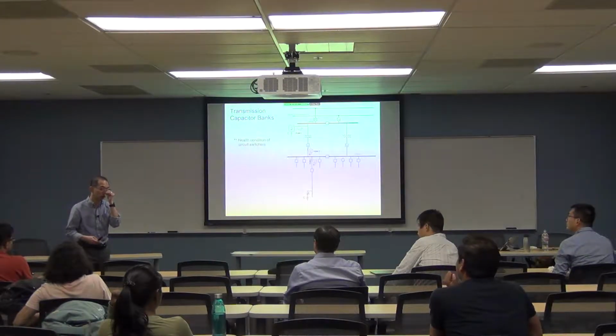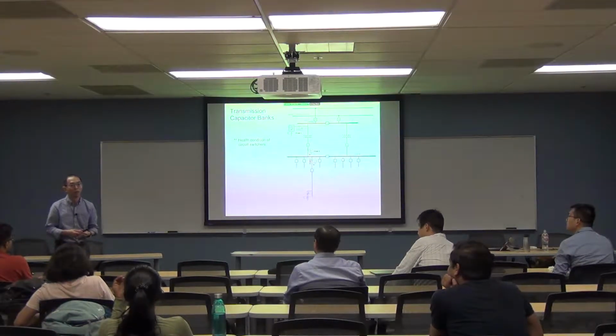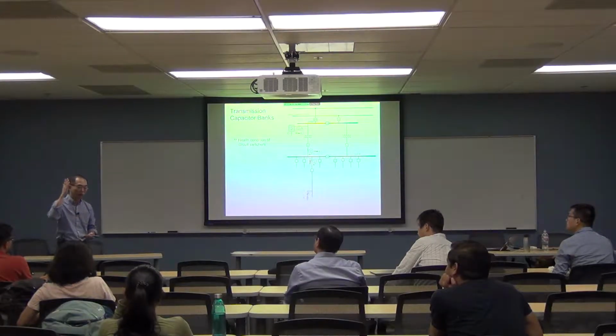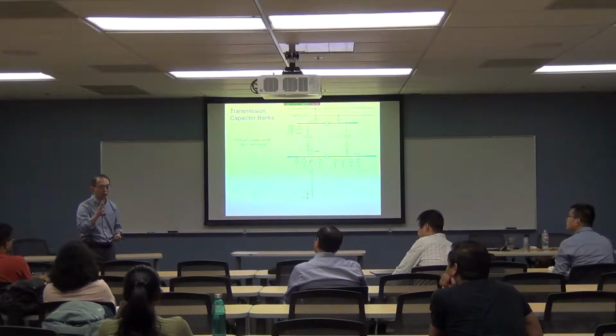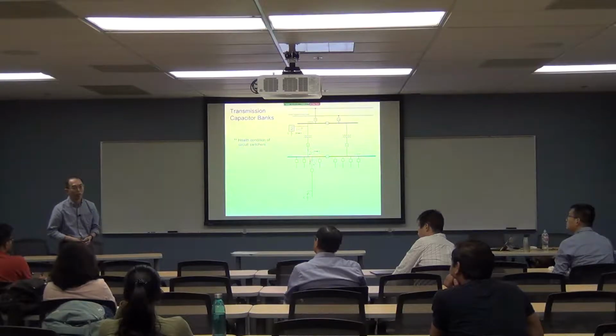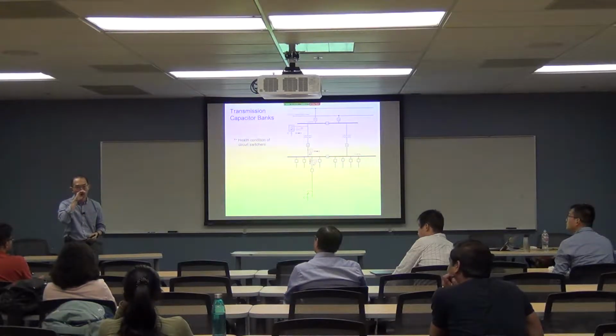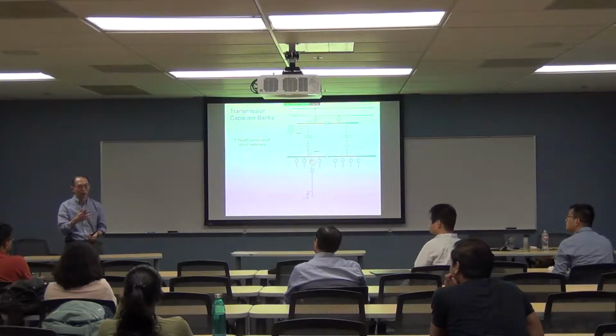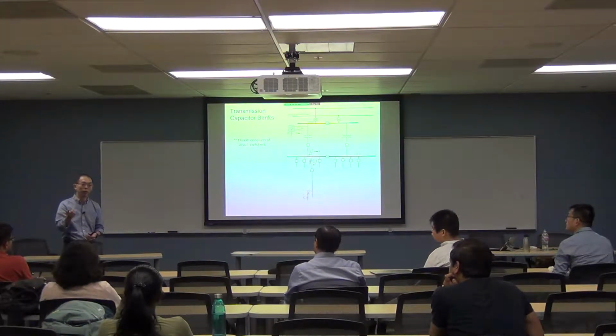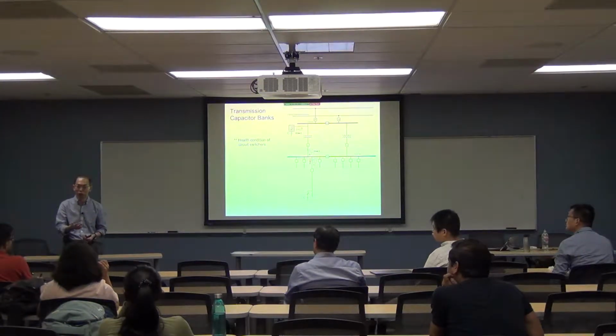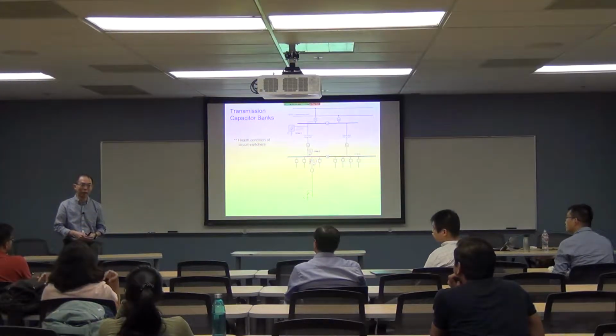Voltage and current analysis, based on the first derivative of the switching instant of the transients. That can only be done if you have sufficient number of samples per cycle, like 256 and higher. If it is measured using a protective relay, which is maybe 32 or 64 samples, you probably cannot get that.